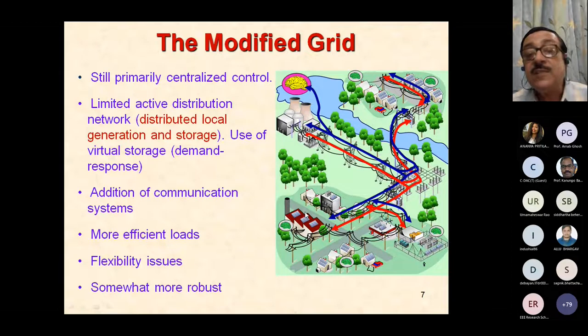Because now, suppose this consumer was originally drawing power from the centralized point, so the current, whatever he's drawing, has to come all the way along the transmission and the distribution network, and that current has certain contribution in the total voltage drop taking place at this point of coupling. If we feed in a power from a local point, then this current disappears, and the current is now flowing in a shorter distance, so the voltage drop at this point is not that much as it was earlier. So you're improving the voltage stability at the local point by local power injection.